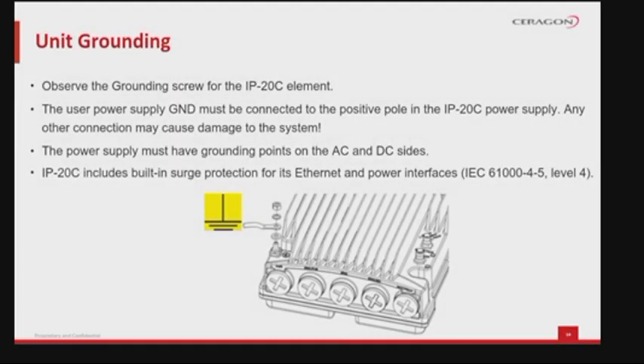To do the unit grounding, follow these steps. 1. On the front of each IP20C unit, loosen the nut, plain washer, and serrated washer from the ground stud, using the metric offset hexagon key and the wrench. 2. Place the cable lug, supplied with the IP20C grounding kit, in place on the screw. 3. Secure cable lug.